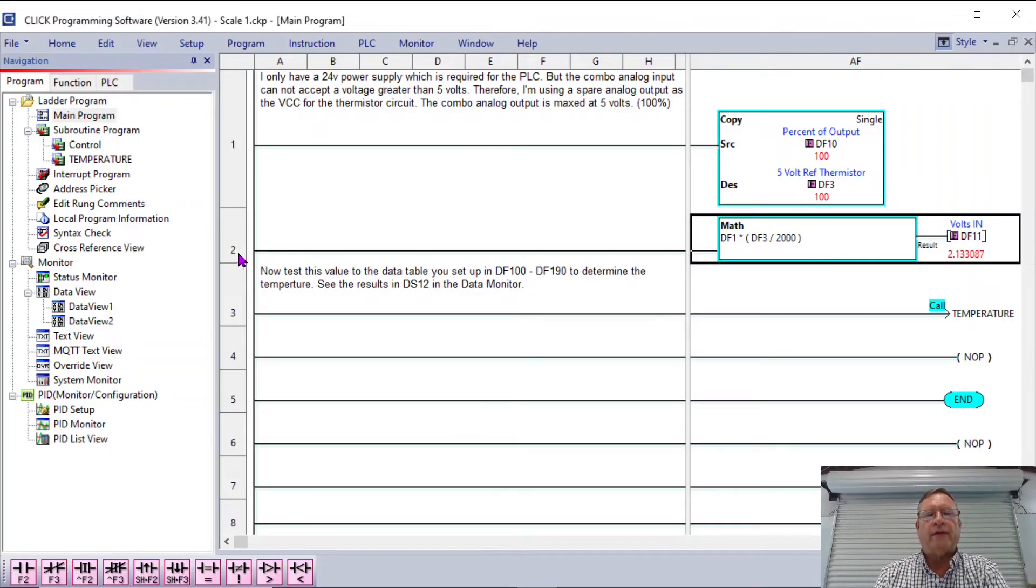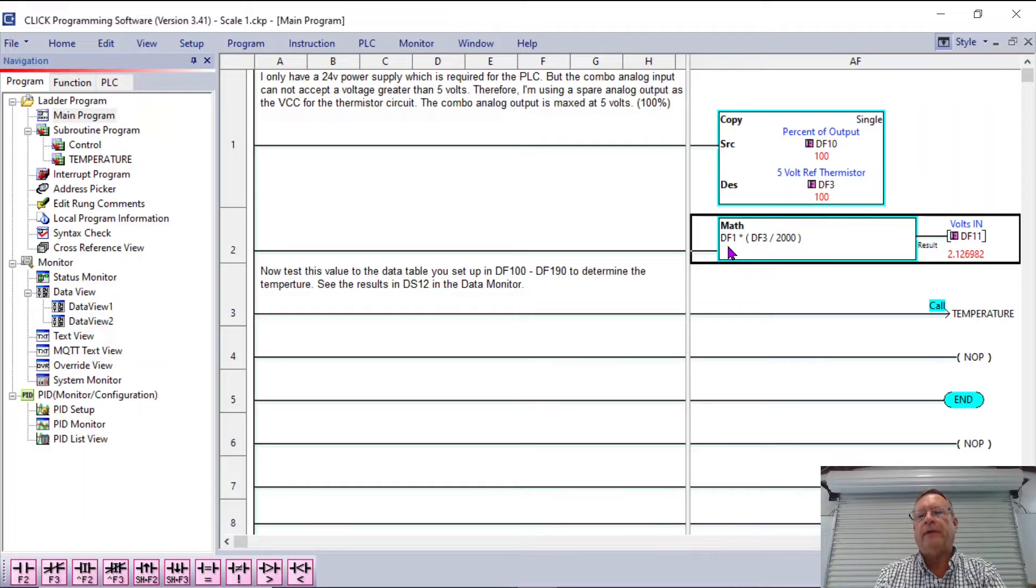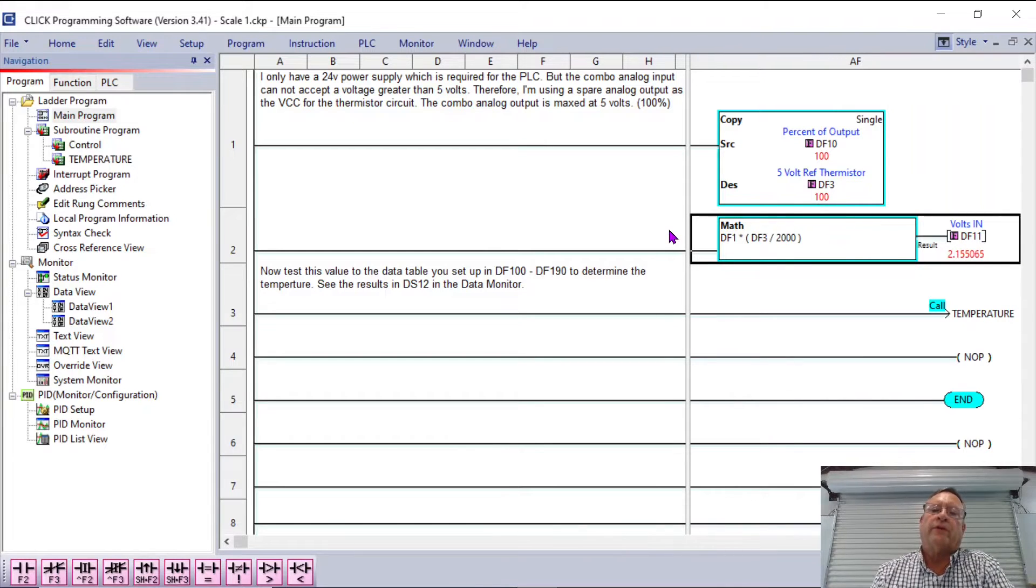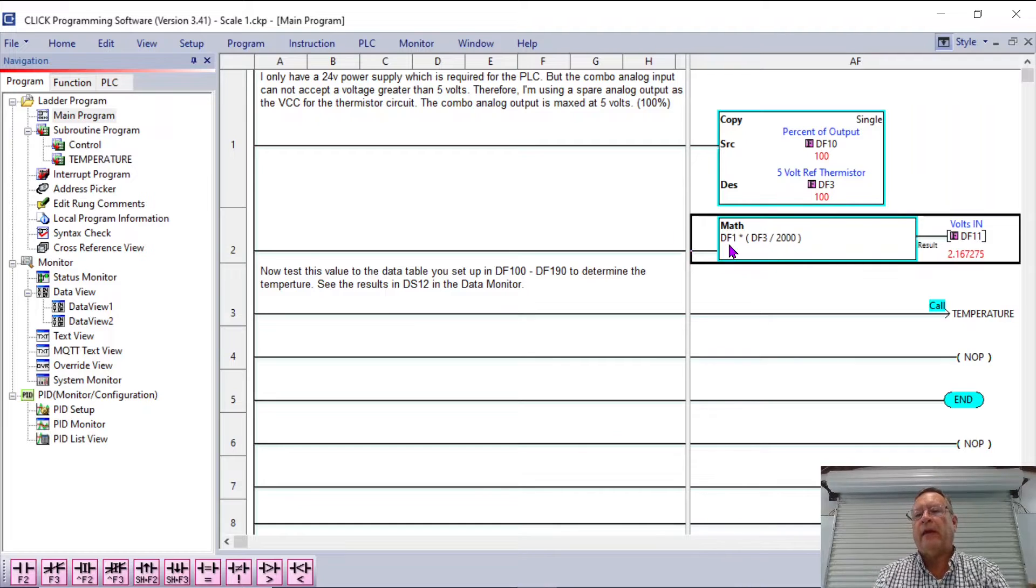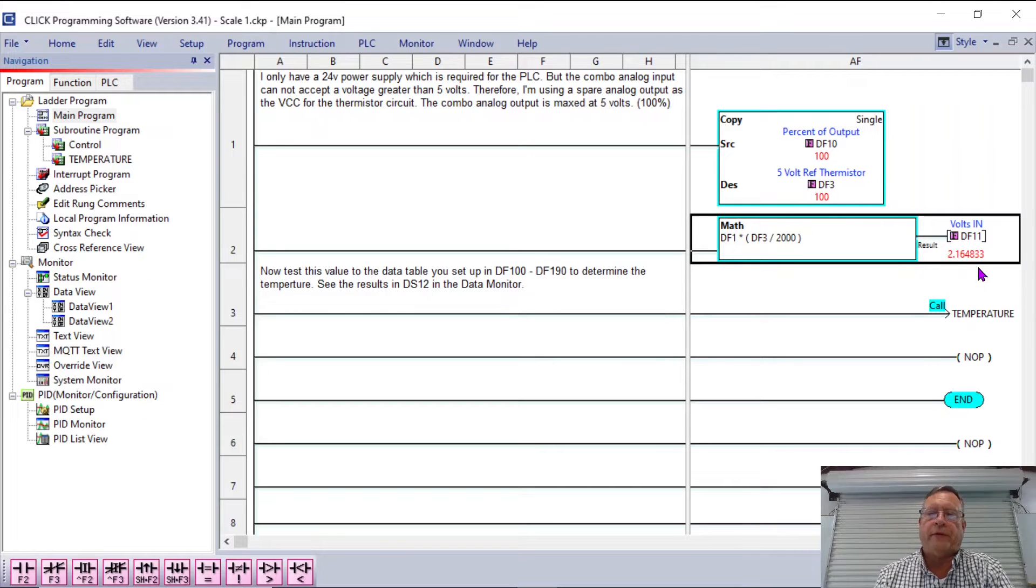Now if you recall in the last video I had to make my own scaling to be able to measure the temperatures from a thermistor because it's nonlinear and the values change for every degree and I wanted to know what it was for every degree for a certain temperature range. But the part that nobody caught me on was this. In the last video I had this rung number 2 and I said it was there because I needed to scale the analog input that was coming into register DF1 and I needed to scale that to volts. This works. It's not necessarily the best way. It does take the value that I have here in DF1 and convert it to the value of range that I wanted.